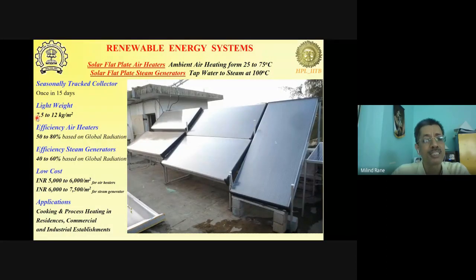Now, the best part is these collectors are very light compared to the conventional collectors. These collectors are almost one half to one third the weight of the conventional collectors. The efficiencies are better than the conventional collectors. For air heaters, even heating up to 80 degrees centigrade, we have achieved efficiencies as high as 75-80% based on global radiation. Efficiency for steam generation has typically been between 40 to 60% depending upon the radiation level.